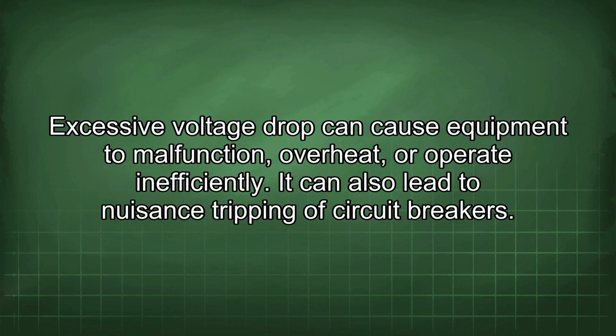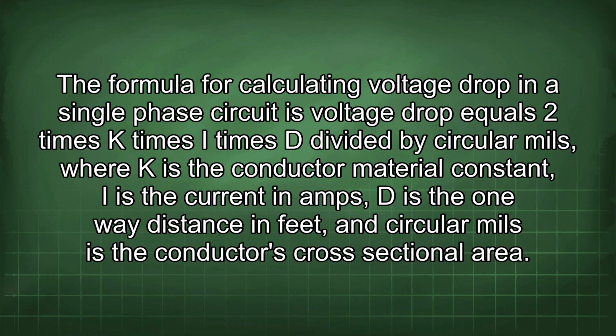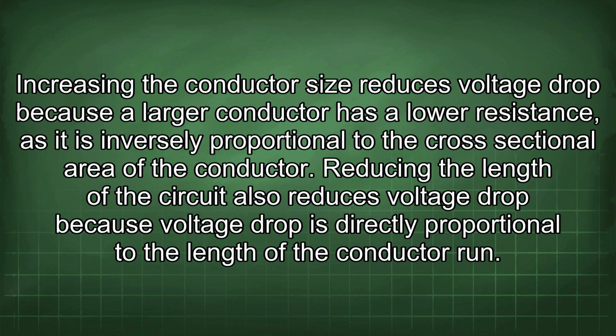Excessive voltage drop can cause equipment to malfunction, overheat, or operate inefficiently. It can also lead to nuisance tripping of circuit breakers. The formula for calculating voltage drop in a single-phase circuit is voltage drop equals 2 times K times I times D divided by circular mils, where K is the conductor material constant, I is the current in amps, D is the one-way distance in feet, and circular mils is the conductor's cross-sectional area. Increasing the conductor size reduces voltage drop because a larger conductor has a lower resistance, as it is inversely proportional to the cross-sectional area of the conductor.